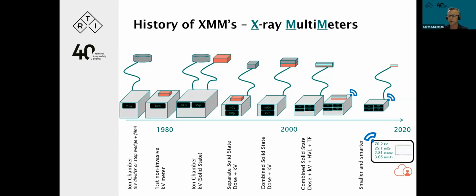Before that, to measure both dose and tube potential, you had to carry around an invasive voltage divider, which took a lot of space and was very cumbersome to deal with. Then throughout the 80s and 90s, the devices became smaller.